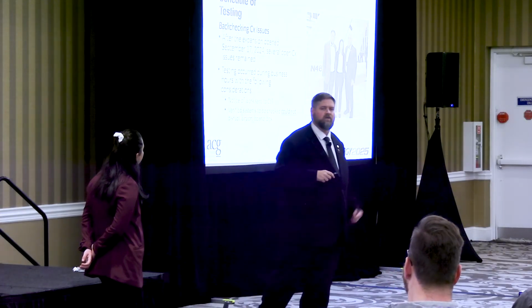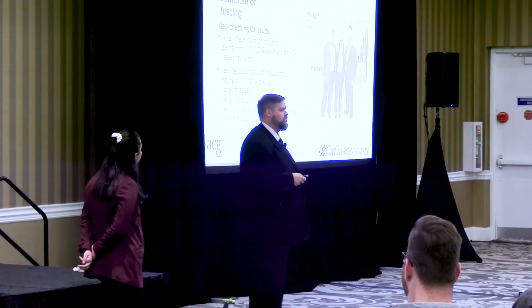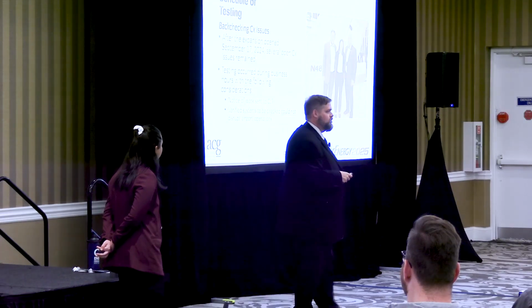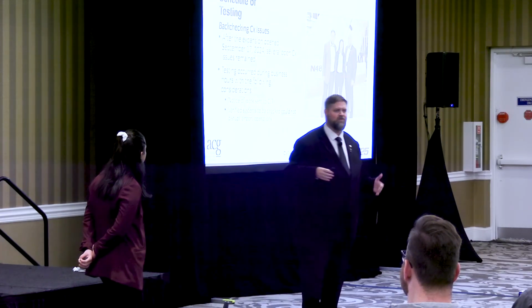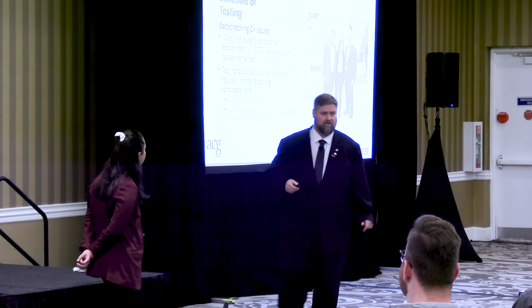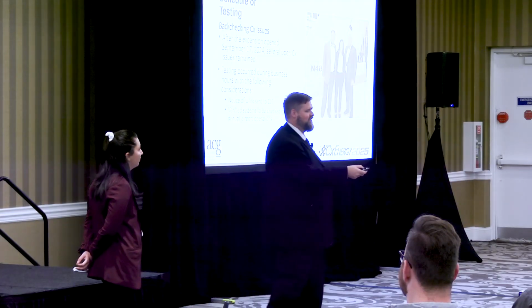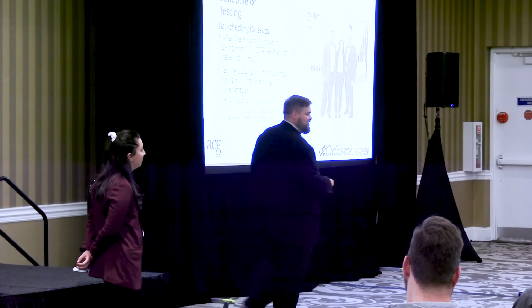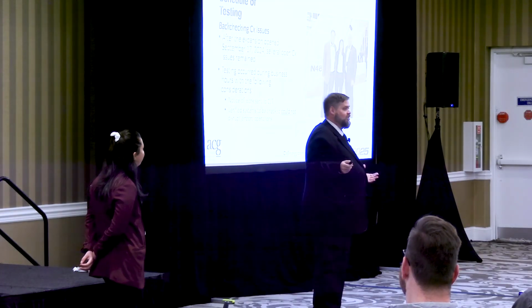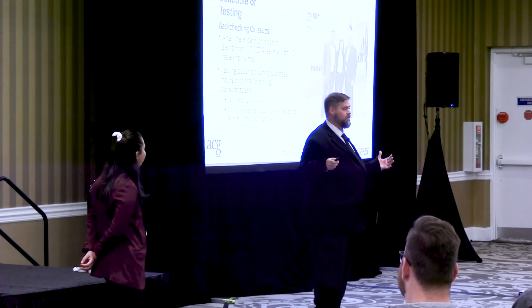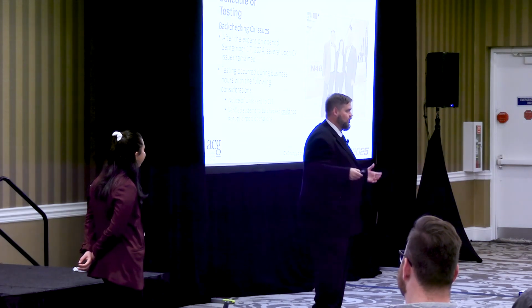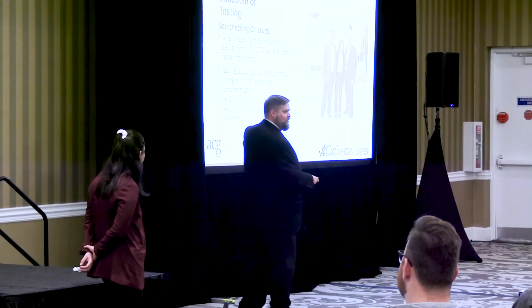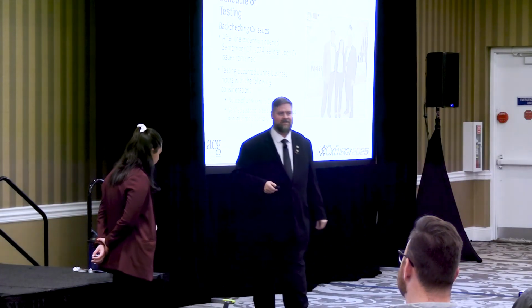There's a running joke I've had with different commissioning providers over the years: how do you know you've tested a chiller plant properly, or an air handling unit? You know the answer, come on, say it, Amy. You shut it down. You do something so that all of a sudden it trips and you go, oh, I didn't expect that to happen. But this note clearly says you're not allowed to do that.